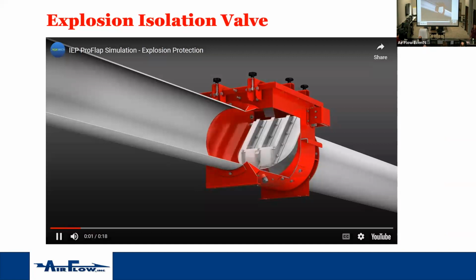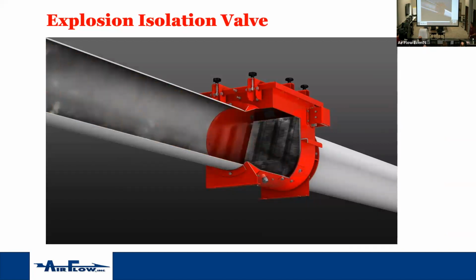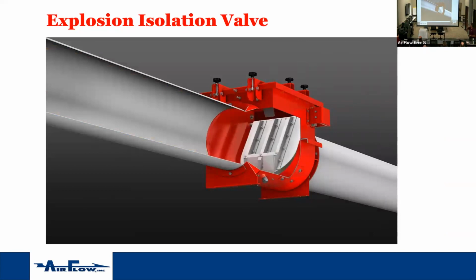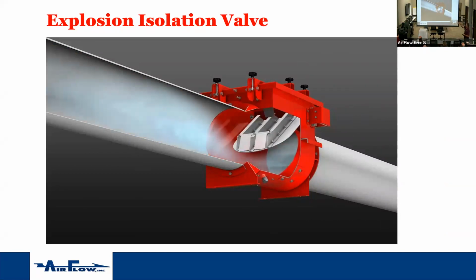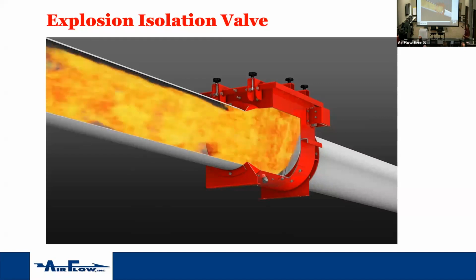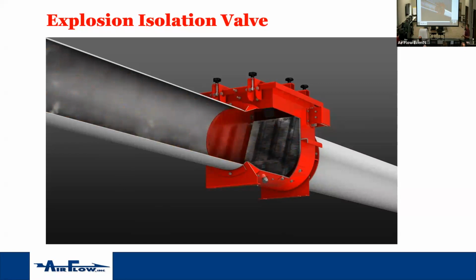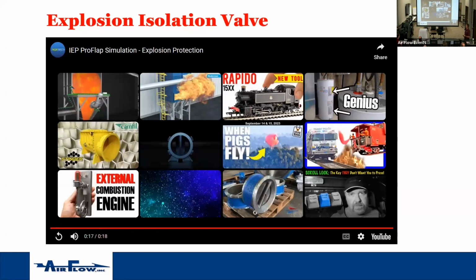Here we go. Perfect, nice work. So if you see it in slow motion here, you'll see the pressure wave come through first. That closes it. The pressure wave closes it and it stops the flame ball from coming through. Pressure is going to travel first before the flame comes through.